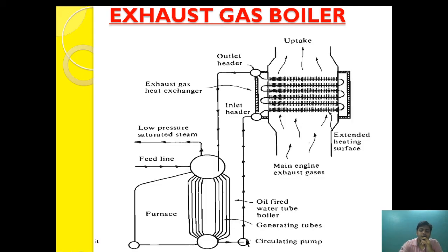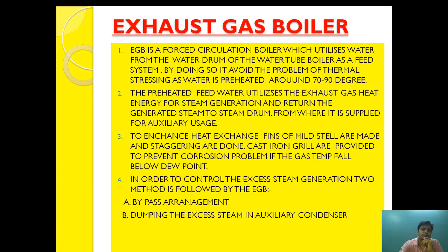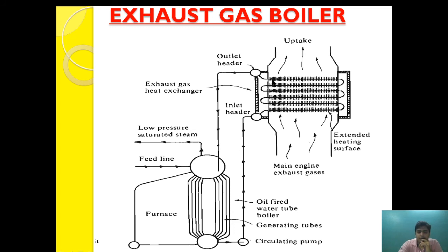By using preheated water from the water drum — around 70 to 90 degrees Celsius — thermal stressing is avoided. Since water is already near boiling point, the conversion to steam is fast and the temperature stress on the tubes is minimal. The preheated feed water utilizes the exhaust gas heat energy for steam generation, and the generated steam is returned to the steam drum for auxiliary uses.